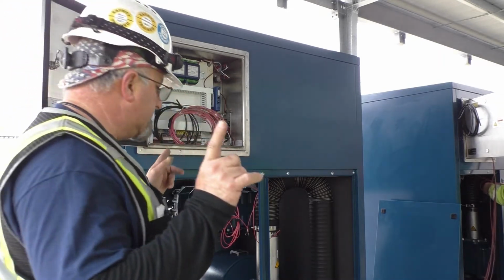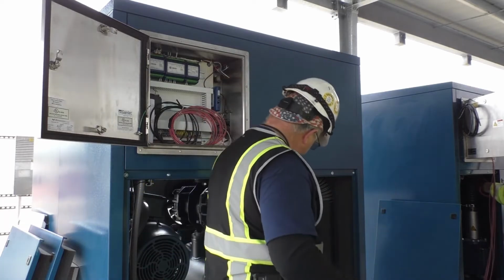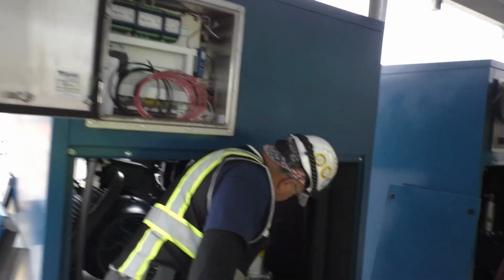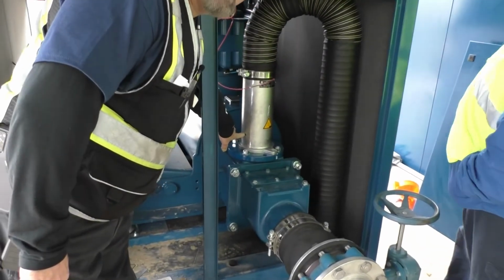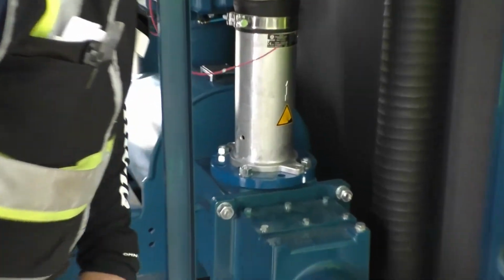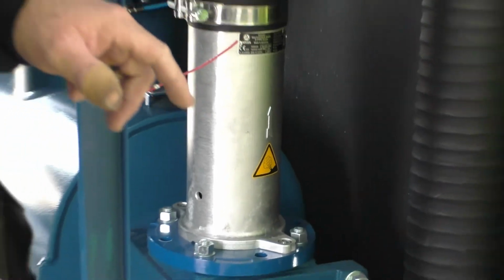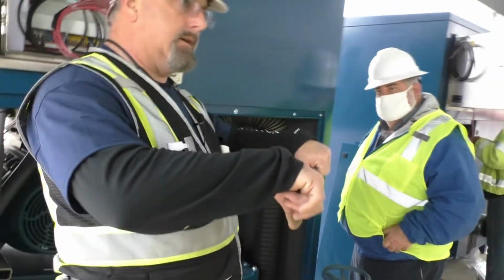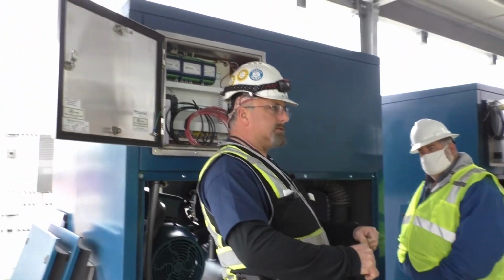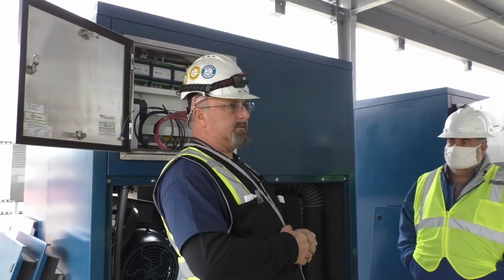All right, the last service item that I want to cover is right here on the pressure relief valve. Every one of them has it. There's 2 holes. What that is for is once a year, with the blower running, take 2 flat tip screwdrivers, lift, let it exhaust, release, make sure it reseals.